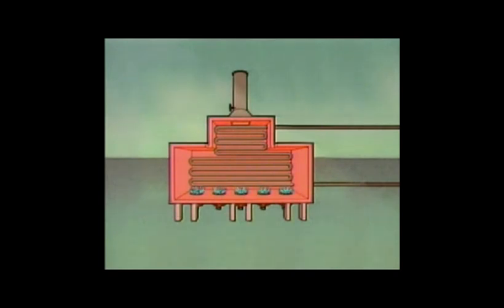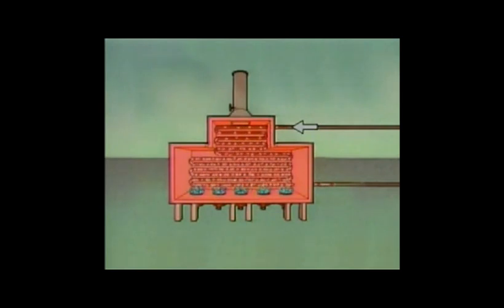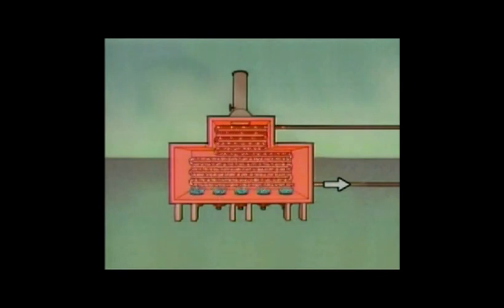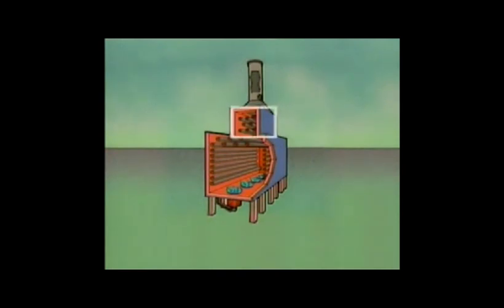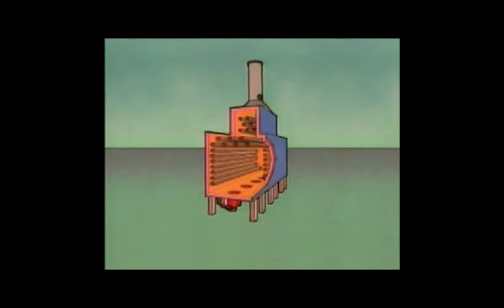Inside this furnace, tubes carry the process fluid through the furnace. The process fluid enters near the stack, passes through the tubes, and leaves near the bottom by the burners. The tubes are grouped into two major areas: the convection section, which is closer to the stack, and the radiant section, which is closer to the burners. The shell of the furnace is lined with a heat-resistant material called refractory.